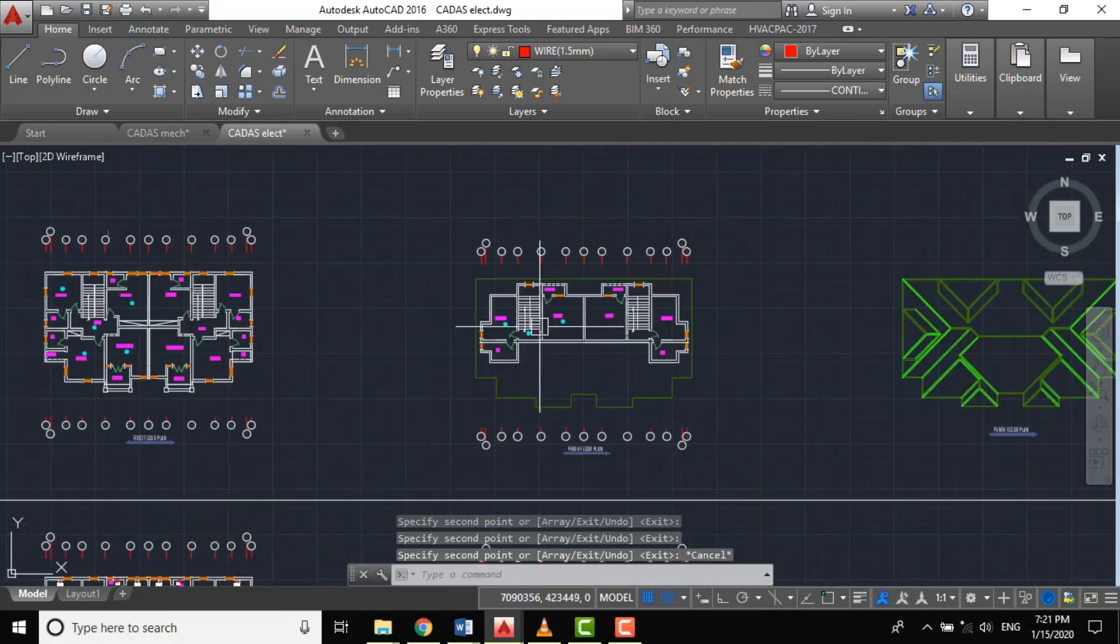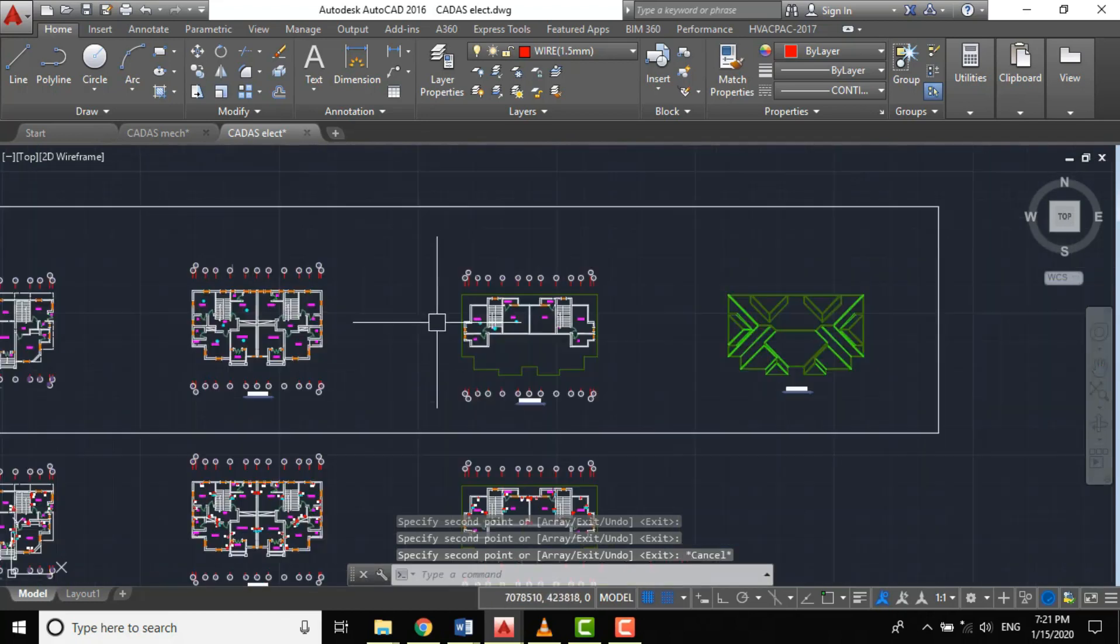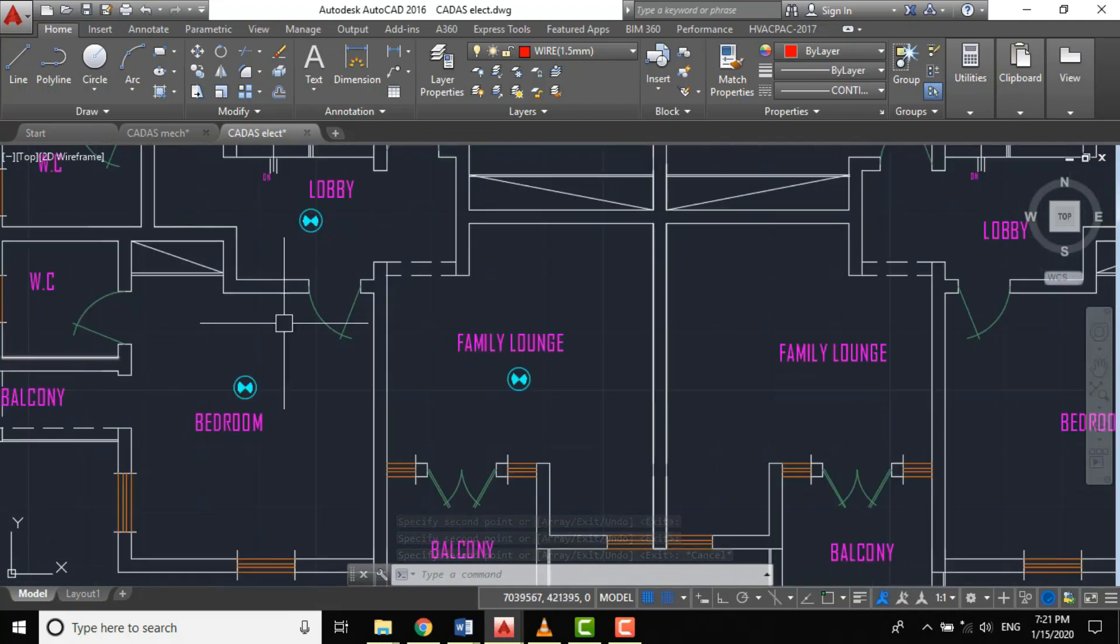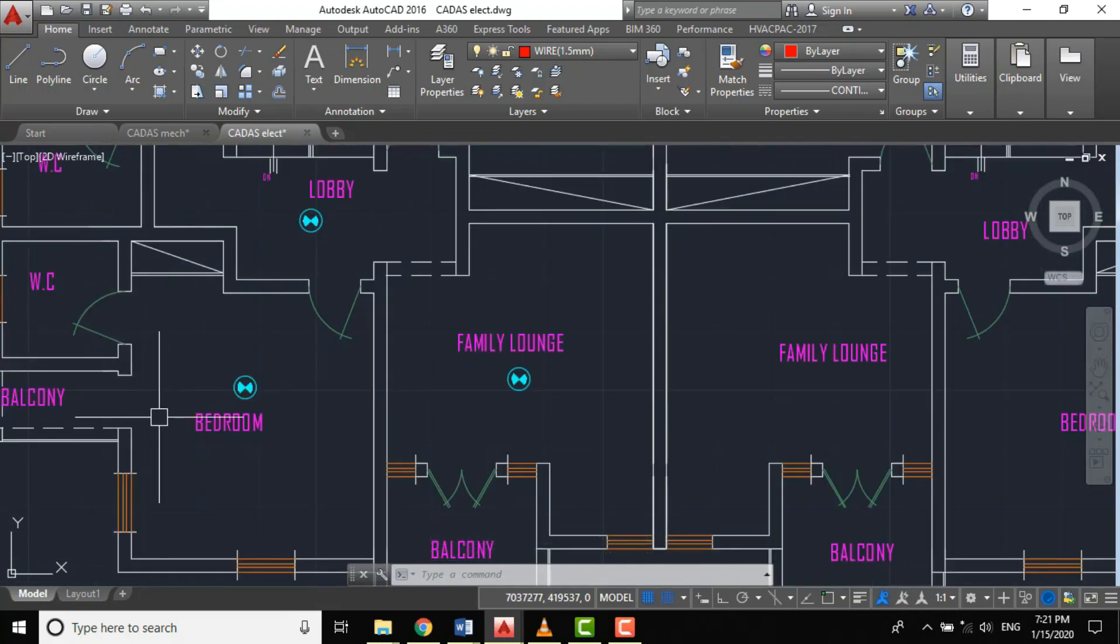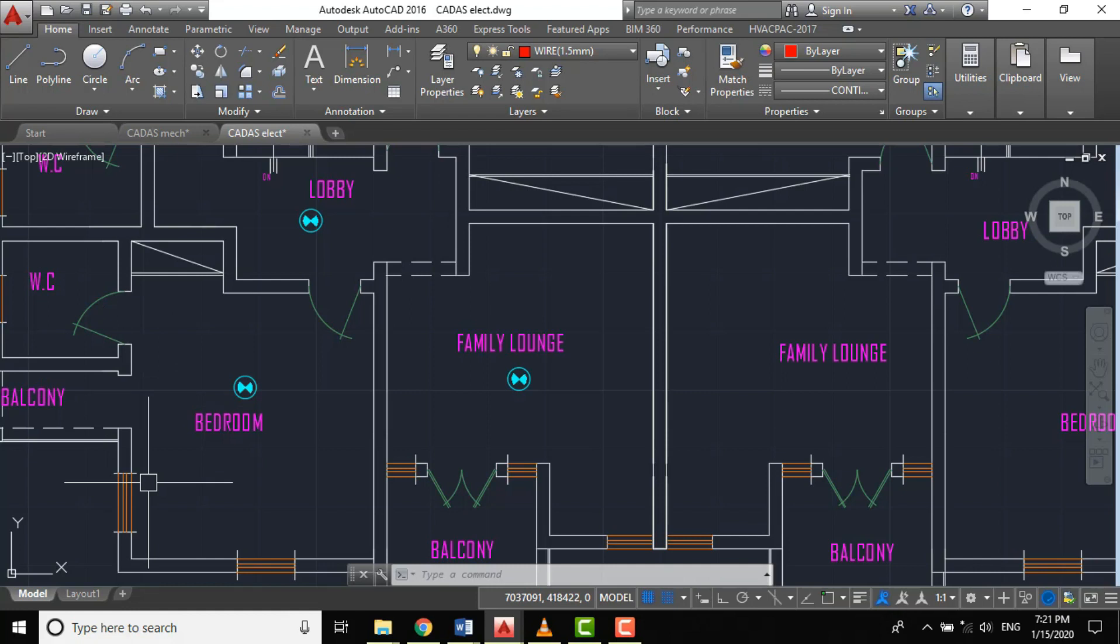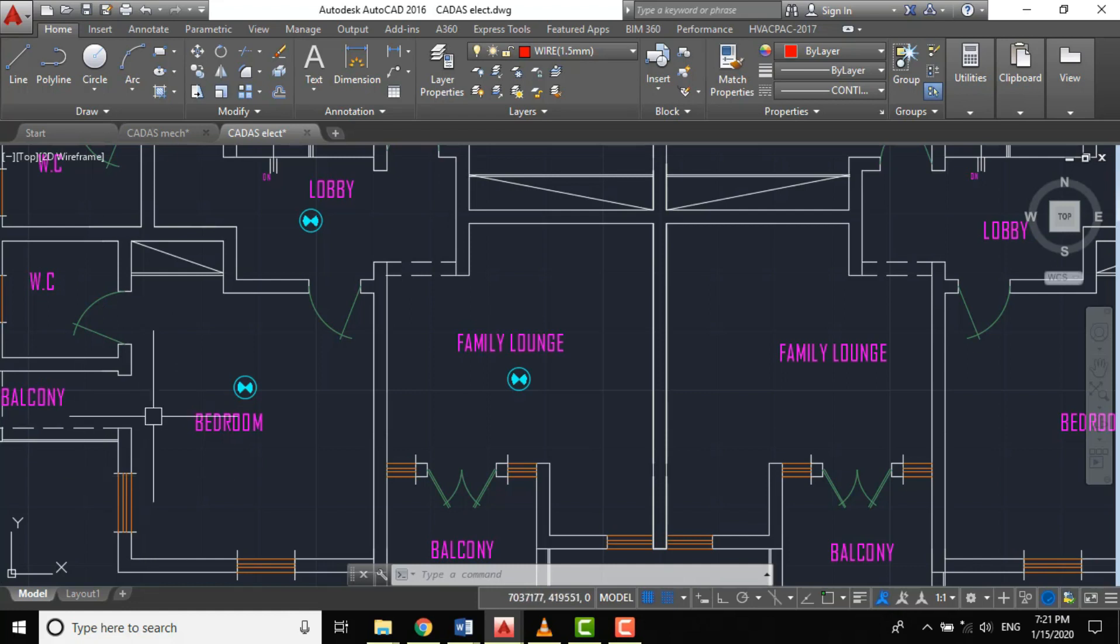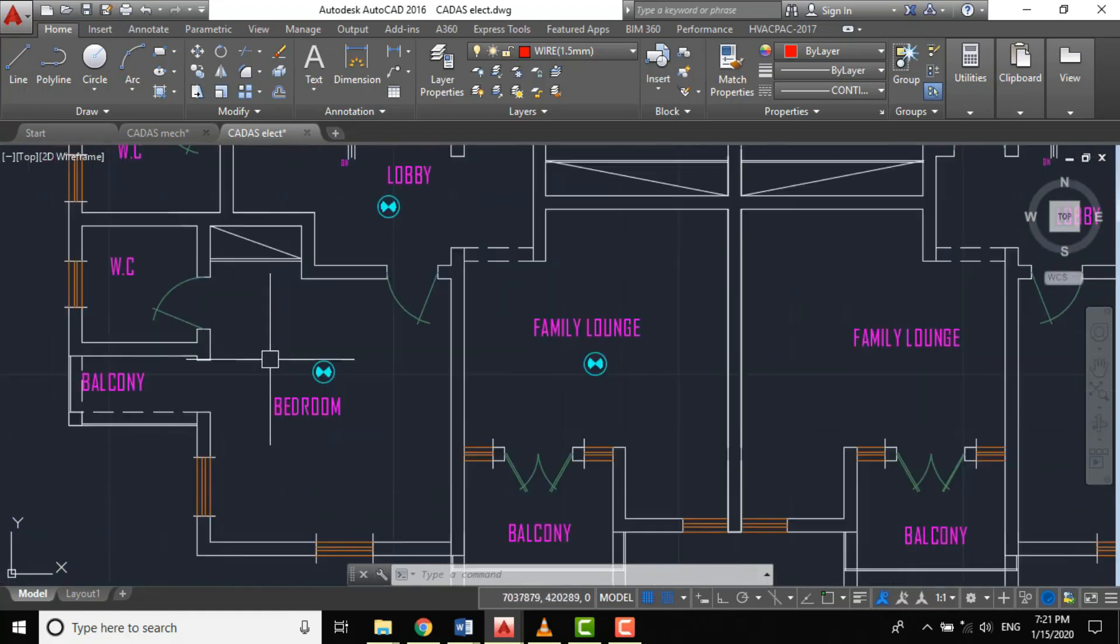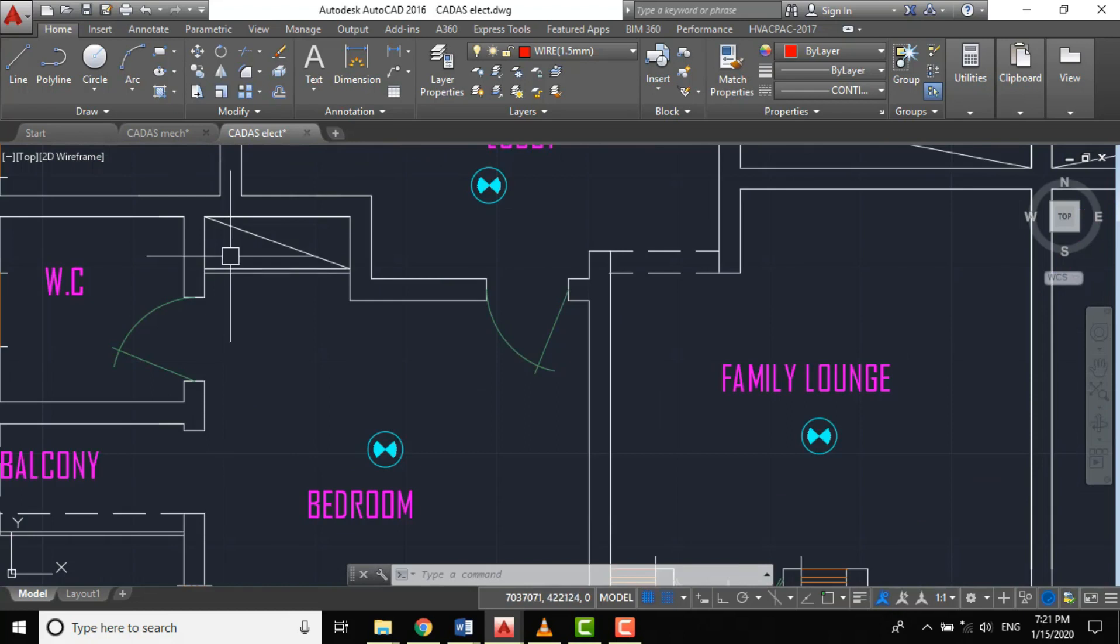One of the basic considerations is that every point in the building must be within the radius of the detector. The radius of the smoke detector will be 7.5 meters.